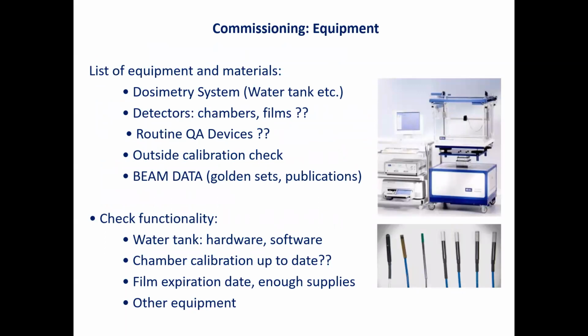Before starting the commissioning, we should list all the required equipment and certainly check its functionality. If we have already given a timeline to the administration to start our clinical service, and today I put my water phantom in and see that my ionization chambers are not working, that would have a very bad impact. So we should check the functionality beforehand.